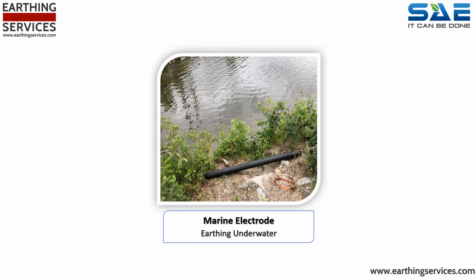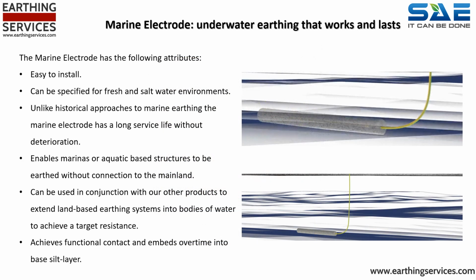We're now going to consider the marine electrode, the most effective way to achieve resistance even without connection to land. The marine electrode has the following attributes. It is easy to install, can be specified for fresh and saltwater environments. Unlike historical approaches to marine earthing, the marine electrode has a long service life without deterioration. It enables marinas or aquatic based structures to be earthed without connection to the mainland. It can be used in conjunction with our other products to extend land-based earthing systems into bodies of water to achieve a target resistance. It achieves functional contact and embeds over time into the base silt layer.